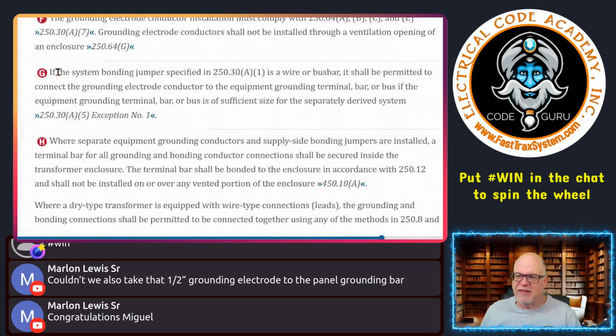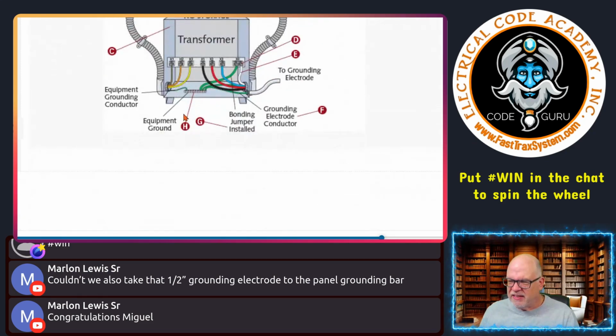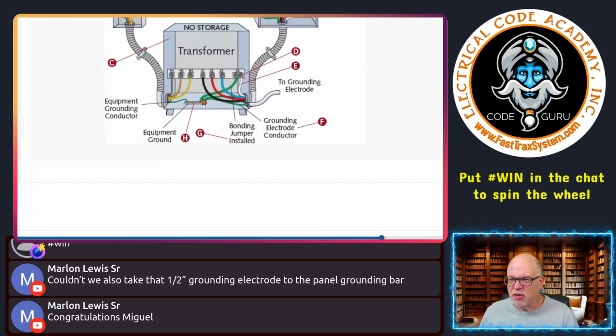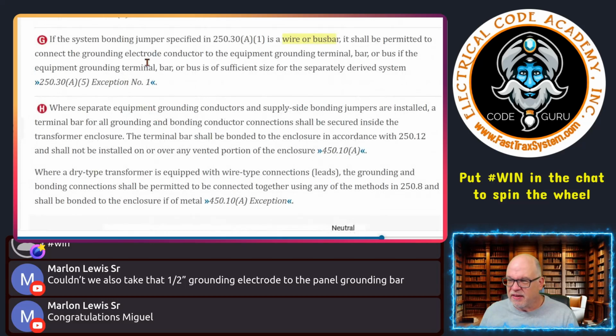It says, if the system bonding jumper specified in 250.30(A)(1) is a wire or bus bar type, it shall be permitted to connect the grounding electrode conductor to the equipment grounding terminal bar or bus if the equipment grounding terminal bar or bus is of sufficient size for the separately derived system.